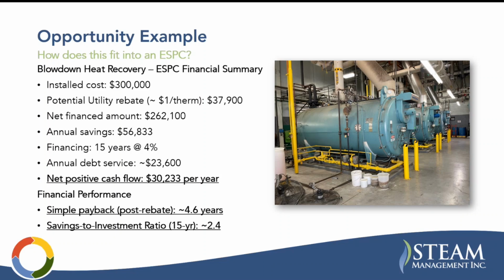Annual savings again, $56,833. With 15-year financing at 4%, you have an annual debt service of $23,600. So you have a net positive cash flow on this opportunity of $30,233 per year. This is a contract driving measure when the variables are conducive. This is a simple payback after the rebate of 4.6 years and a savings to investment ratio of 2.4.